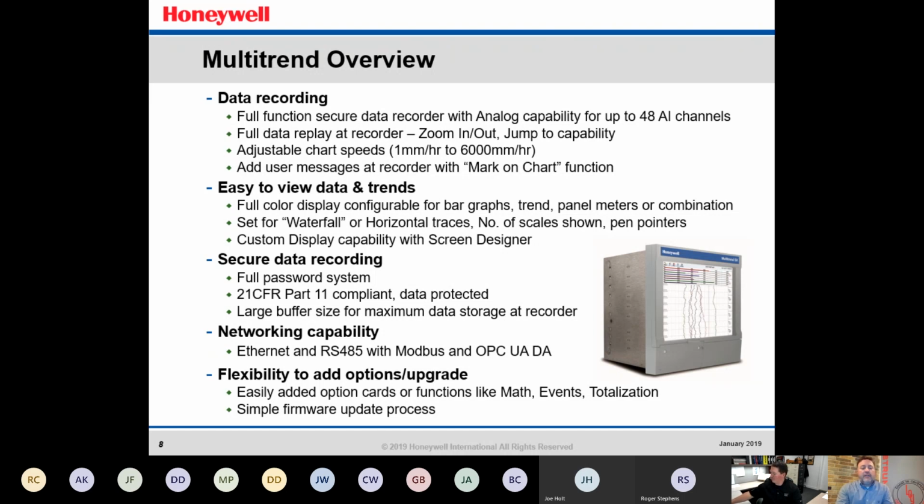Secure data recording. The data is all encrypted, and we needed to have that for several different reasons. One of the largest reasons is for the pharmaceutical industry. When they are trying to meet the 21 CFR Part 11 compliancy, the data needs to be encrypted and protected in a certain fashion so that nobody could mess with the data and change the values. So that was one of the biggest parts of helping get this recorder to that level so that it could be used in the pharmaceutical industry and other industries that utilize the 21 CFR Part 11.